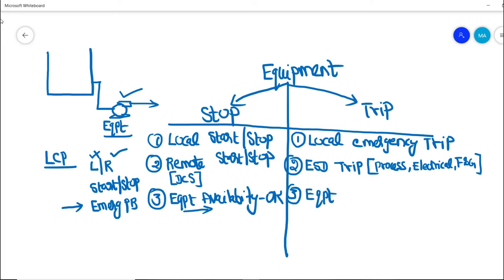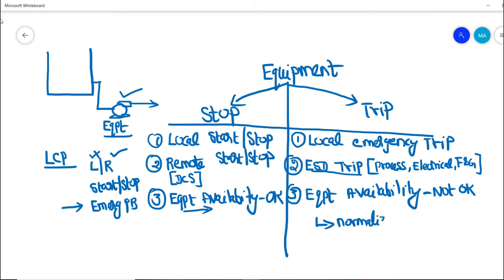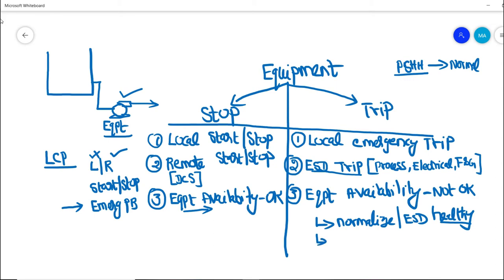In both local emergency push button trip and ESD trip, the equipment availability becomes not okay. If an equipment trips, you cannot start it again without normalizing the ESD trip. There are two things we have to do: first, normalize or make the ESD healthy. For example, if a process high-high initiated the ESD trip, you have to normalize the PSHH to its normal operating condition — then only the ESD trip will become healthy.